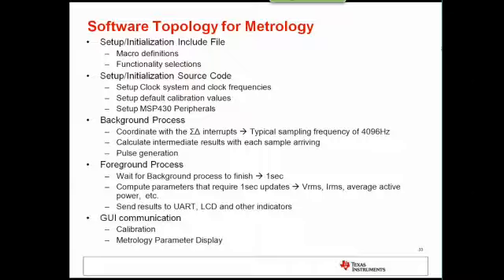There is the background process, which occurs every ADC interrupt. In this process, for each sample that arrives, you update the working parameters for metrology variables, and pulse generation is also done here. In the foreground process, once you have approximately 1 second of data, you compute parameters that require 1 second updates, such as VRMS, IRMS, average active power, average reactive power, and so on. The 5th part is the GUI communication, and the GUI is used for calibration and also for displaying the metrology parameters.